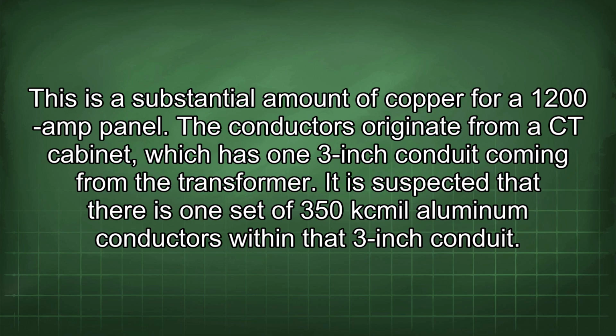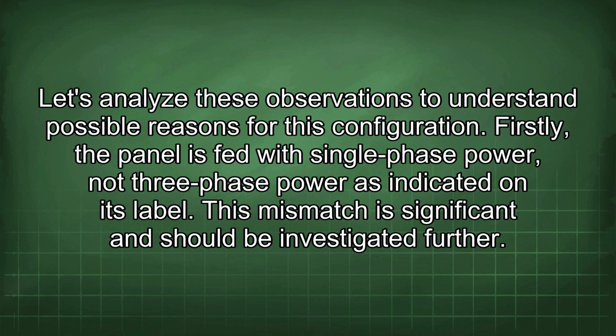The conductors originate from a CT cabinet, which has one 3-inch conduit coming from the transformer. It is suspected that there is one set of 350 kcmil aluminum conductors within that 3-inch conduit. Let's analyze these observations to understand possible reasons for this configuration. Firstly, a panel is fed with single-phase power, not 3-phase power as indicated on its label. This mismatch is significant and should be investigated further.